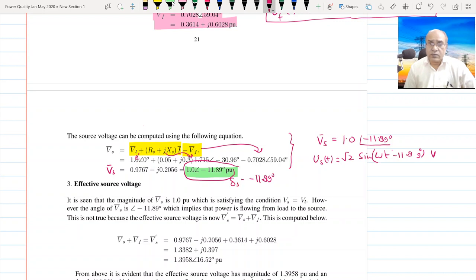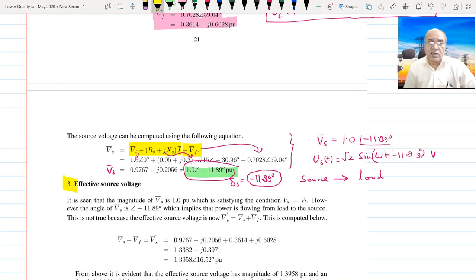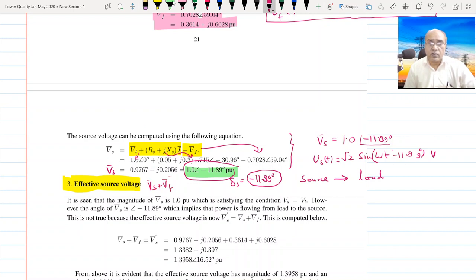You may get confused here because the angle of the source is −11.89°. Can power flow from the source to the load with this negative delta? You have learned that power can only flow when the source angle is positive relative to the load angle, but here it is negative. This confusion will be cleared once we understand the concept of effective source voltage, because Vs is not the only source now — the effective source is the sum of Vs + Vf.